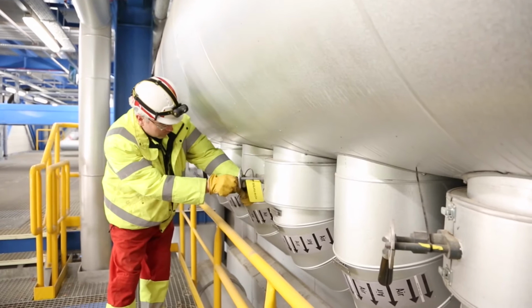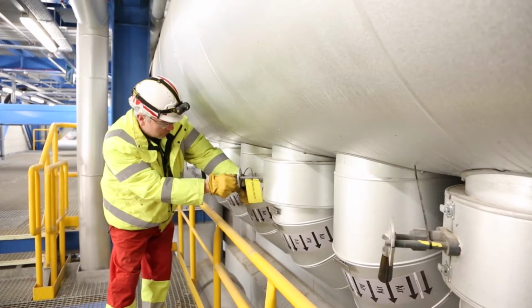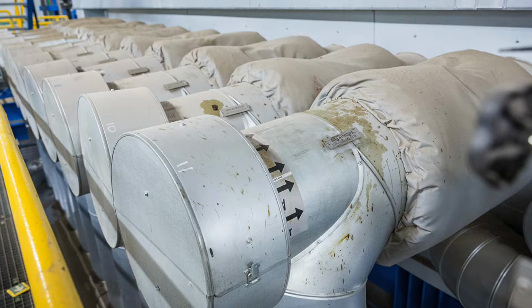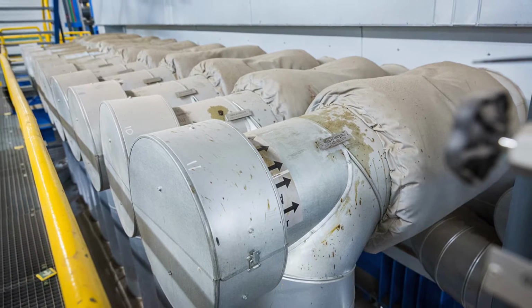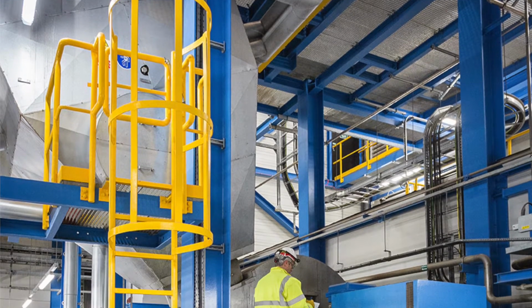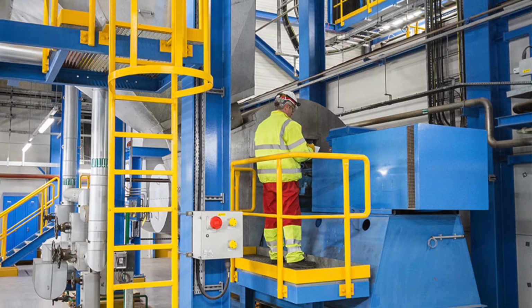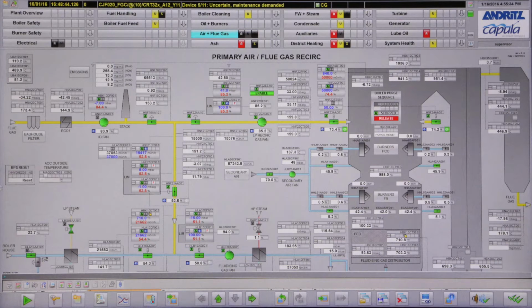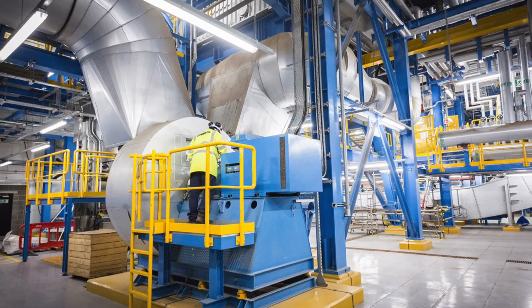The applied combustion technology is the EcoFluid bubbling fluidized bed. The main feature of this technology is the principle of staged combustion of the fuel. The oxygen level in the fluidized bed is limited, and hence only a part of the fuel is combusted, whereas the rest of the fuel is gasified. This can be achieved by adding only a substoichiometric amount of oxygen, approximately 0.35 lambda, to the fuel. In order to maintain the fluidization at an optimum level, at part load conditions and when firing fuels with high heating values, for example, to necessitate less primary air for combustion, recirculation gas is added to the fluidization air.